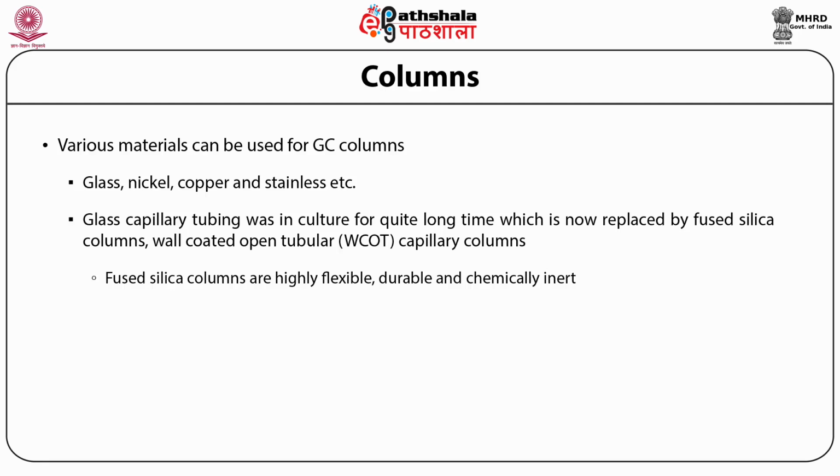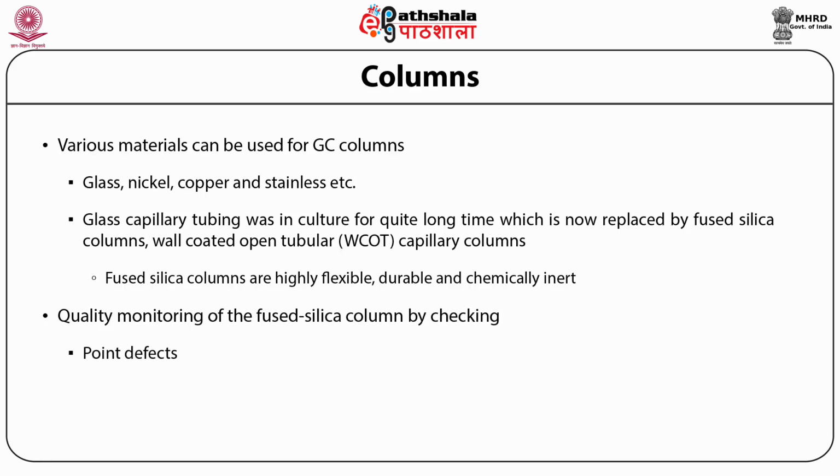And these fused silica columns were based on fiber optics technology. In recent times, packed columns have almost completely been replaced by flexible fused silica tubings, wall coated open tubular, that is WCOT capillary columns. Quality monitoring of the fused silica column is done by checking the point defects and general strength of the capillary tubing.